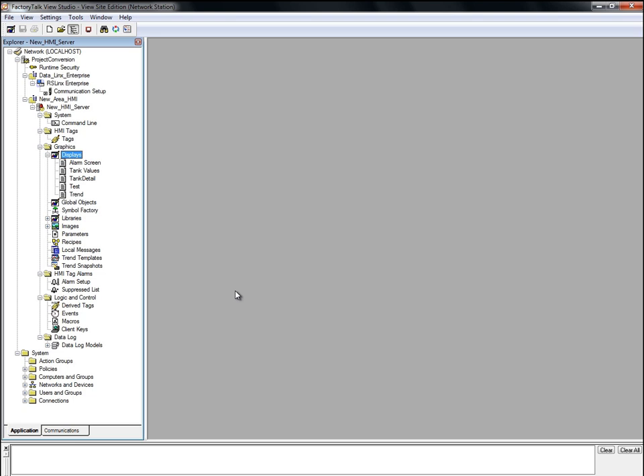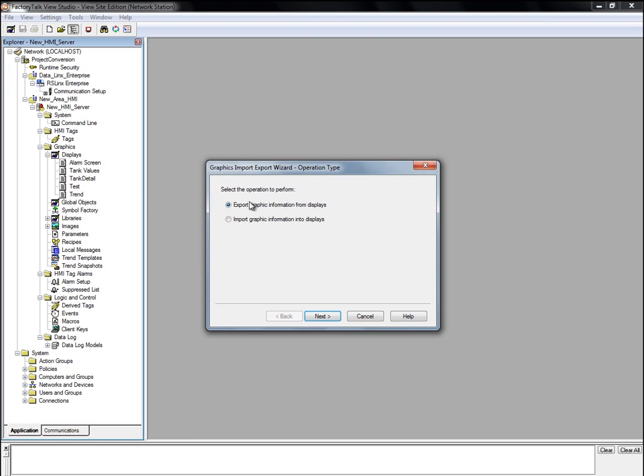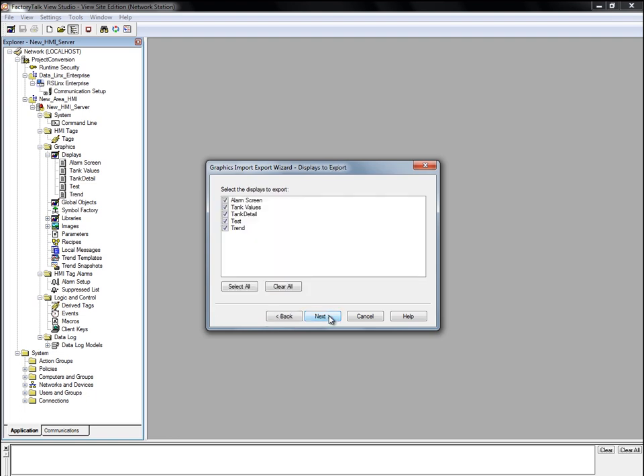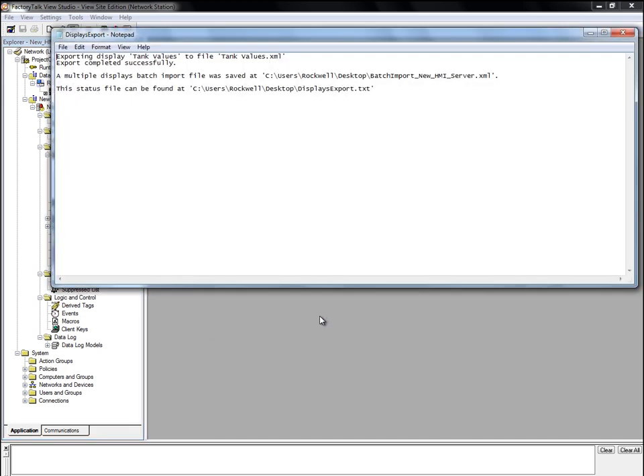The next step is to export the displays to XML format. To do this, you right-click on Displays and choose Import and Export. We want to export graphic information from displays, so we'll pick that. For our example, we will only be changing the Tank Values display. So we'll clear all other displays and just select the one we want. We click Next and then Finish to export the display to an XML file.